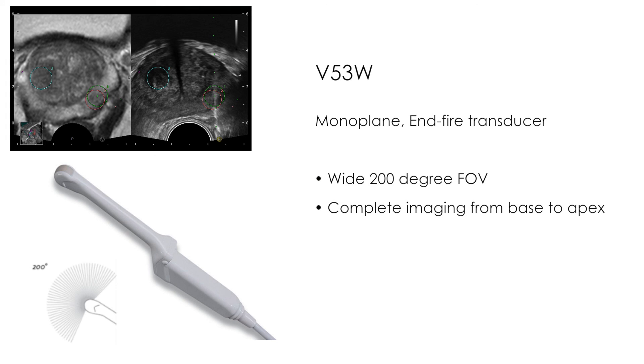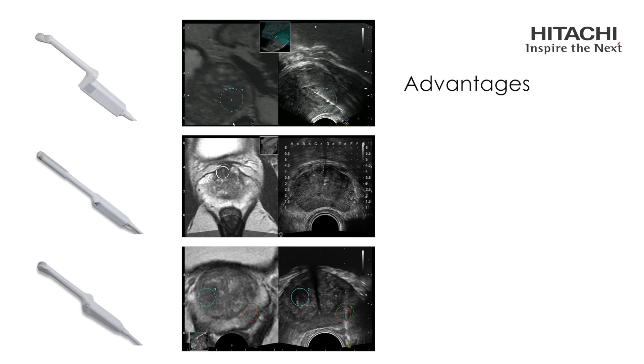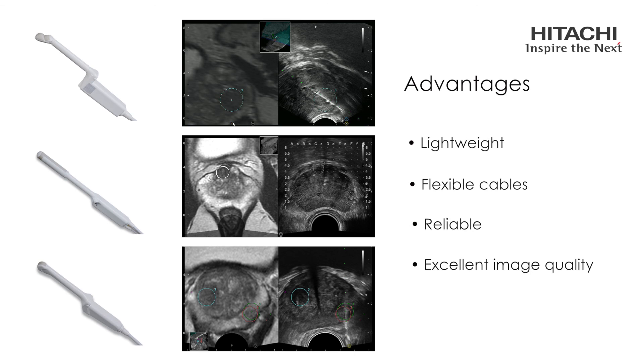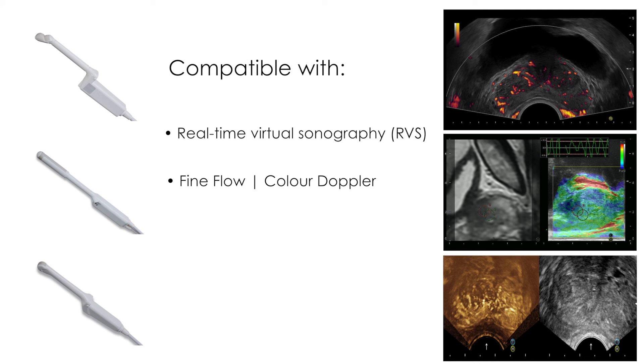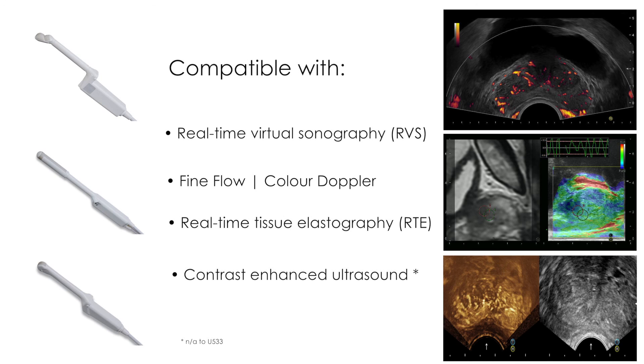The V53W is a monoplane end-fire transducer generating a wide 200 degree field of view for complete imaging from base to apex. All are lightweight in design with flexible cables, delivering reliability with excellent image quality, and are compatible with advanced technologies such as real-time virtual sonography, fine flow and colour Doppler, Hitachi real-time tissue elastography, and contrast-enhanced ultrasound.